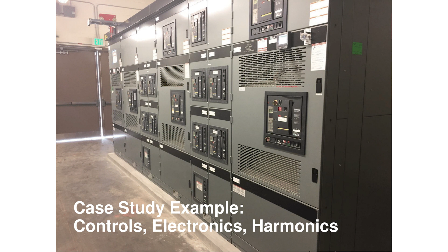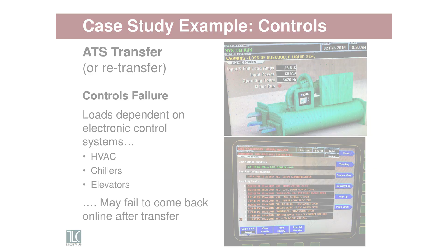One of the things we find is there's a lot of controls failures because things didn't have UPS backups, or lost their programming, or just got confused when switching back and forth for power. So we end up causing problems for the HVAC guys a lot of times because we've switched power back and forth, and things failed that we didn't know were going to. That's why we do integrated systems testing.